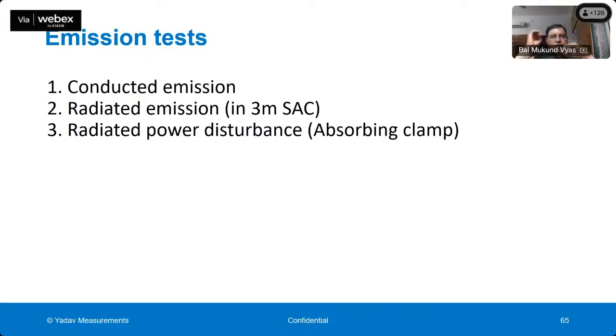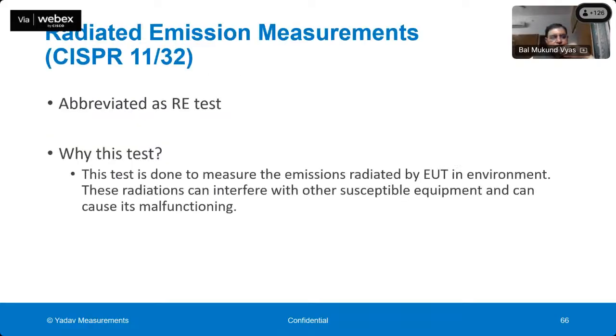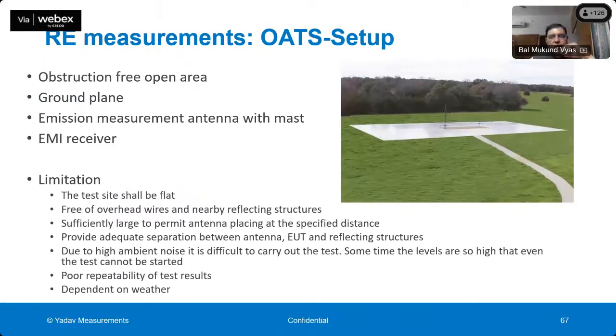Another test, as I was telling, is the emission test: how much radio frequency the meter is emitting. There are three kinds of test: conducted emission, radiated emission, and radiated power disturbance, which can also be measured using an absorbing clamp. This test is done as per CISPR 11 or CISPR 32, and the standard is selected depending on the configuration of the meter.